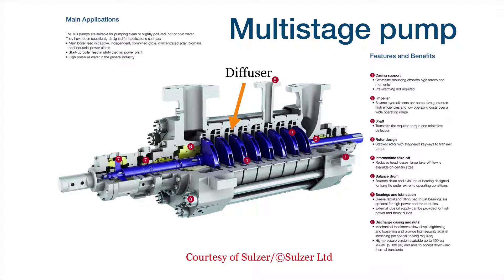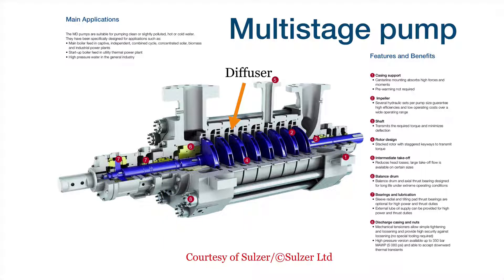This is a typical application — a pump typically used for boiler feed water pumps. Note that this pump is centerline mounted, because the fluid passing through the pump is a hot fluid — boiler feed water in this case. The single-stage pump we saw before was an overhang pump, because the impeller was suspended at the end of the shaft. But here we have a between-bearings pump: one bearing here, another bearing here, and in between we have the impellers. This is the usual configuration for multi-stage pumps, which will be covered in the course on types of pumps.